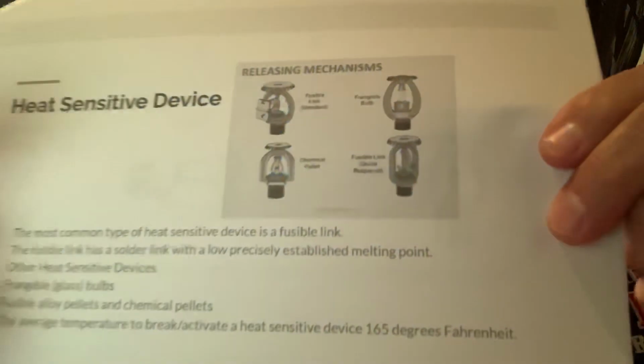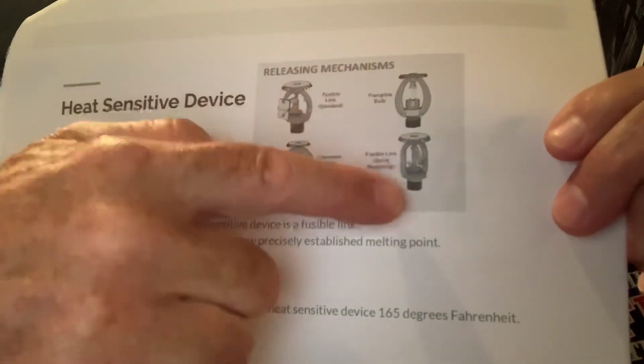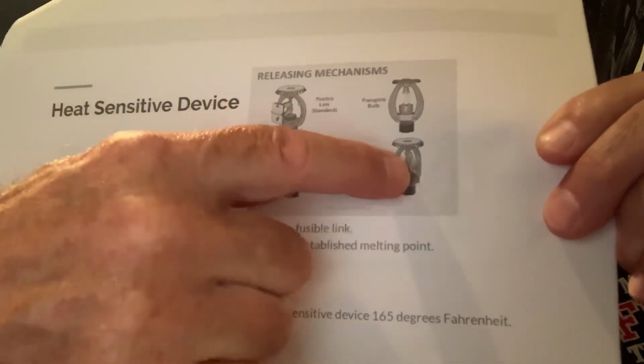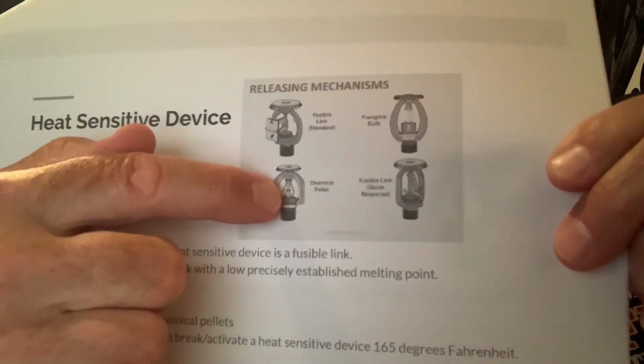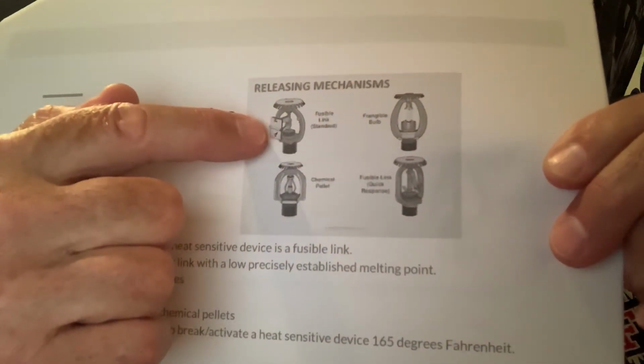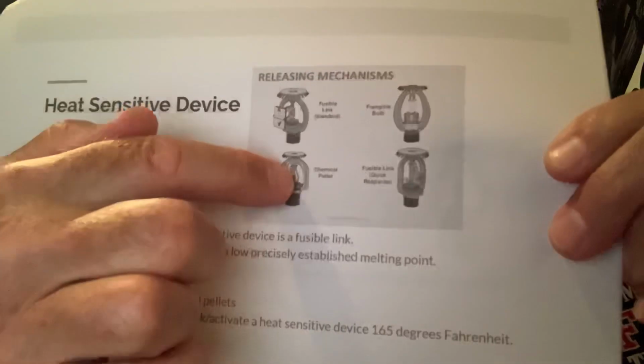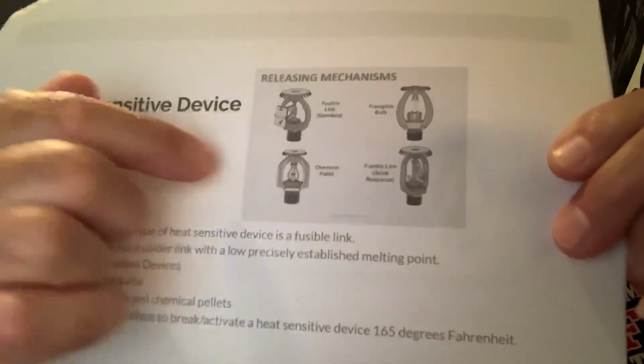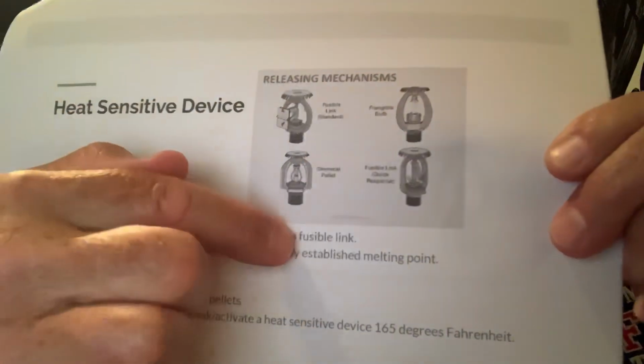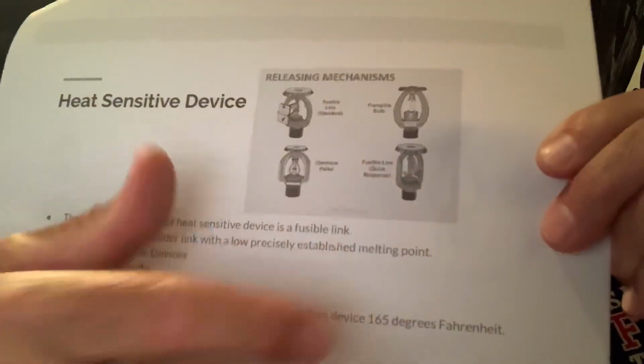Then your heat-sensitive devices. Here's your regular releasing mechanism. Did a good picture of that. There's the different types where it has the deflector component on top. See the deflector component like an umbrella. Okay, so it will activate. If it's a frangible bulb, or in this case chemical pellets, these will melt. The water will pop and flow through here, bounce off the deflector and flow down. Okay, the same thing here is your frangible bulb. There's that solder pellets. There's your frangible bulb, where the glass gets heated in there. That glass will break, and then water will flow, bounce off the deflector component, and spray water downward. Okay, so that's your heat-sensitive devices.